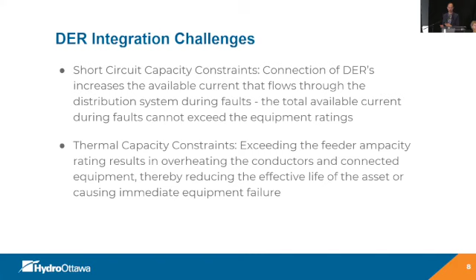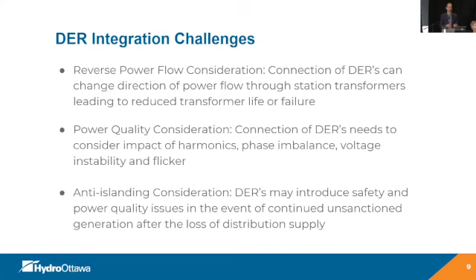With respect to reverse power flow, we can upgrade that equipment, or we can start to adjust loading on those feeders. Power quality considerations, we highly stress meeting the CSA and IEEE standards in order for that equipment to have the minimal impact on our systems. And for anti-islanding, we currently at Hydro Ottawa require the installation of transfer trip for DERs so that they can go offline if there's a loss of the utility. We're also exploring using reverse power flow protection to protect our system as well as the customer's generating site.